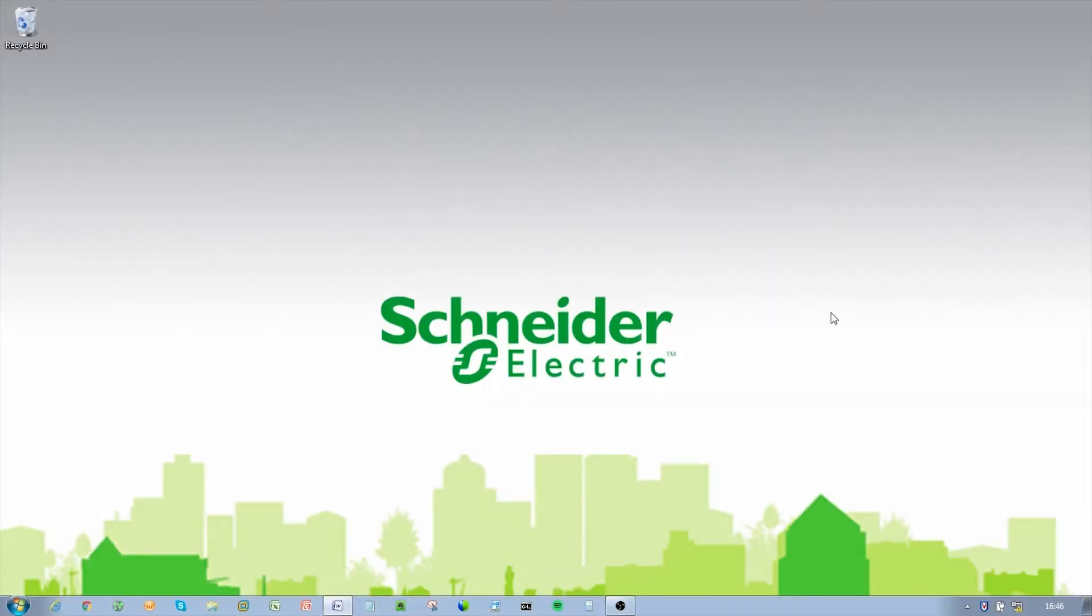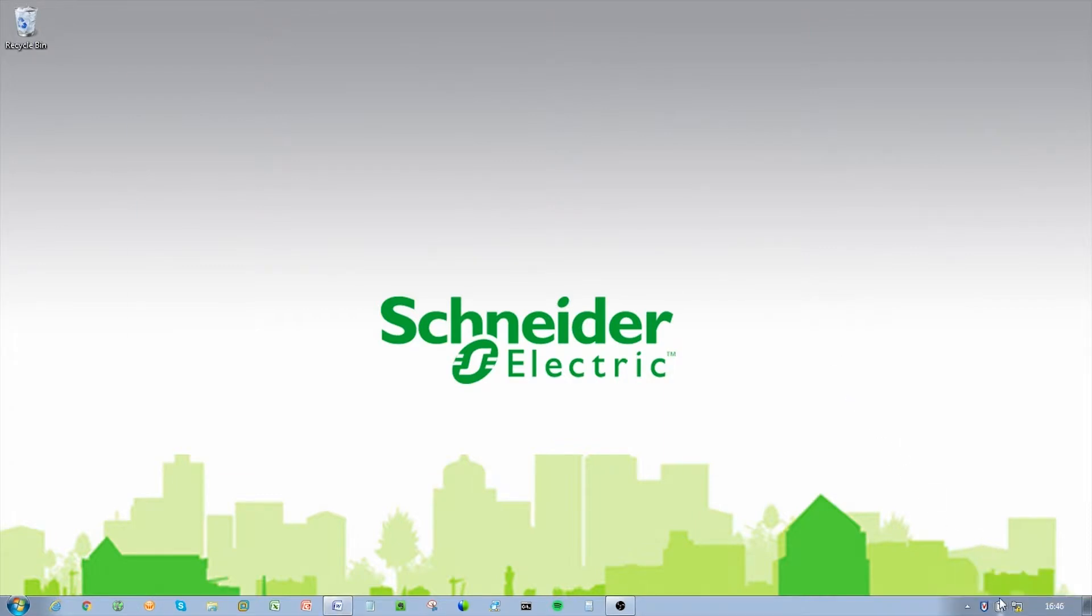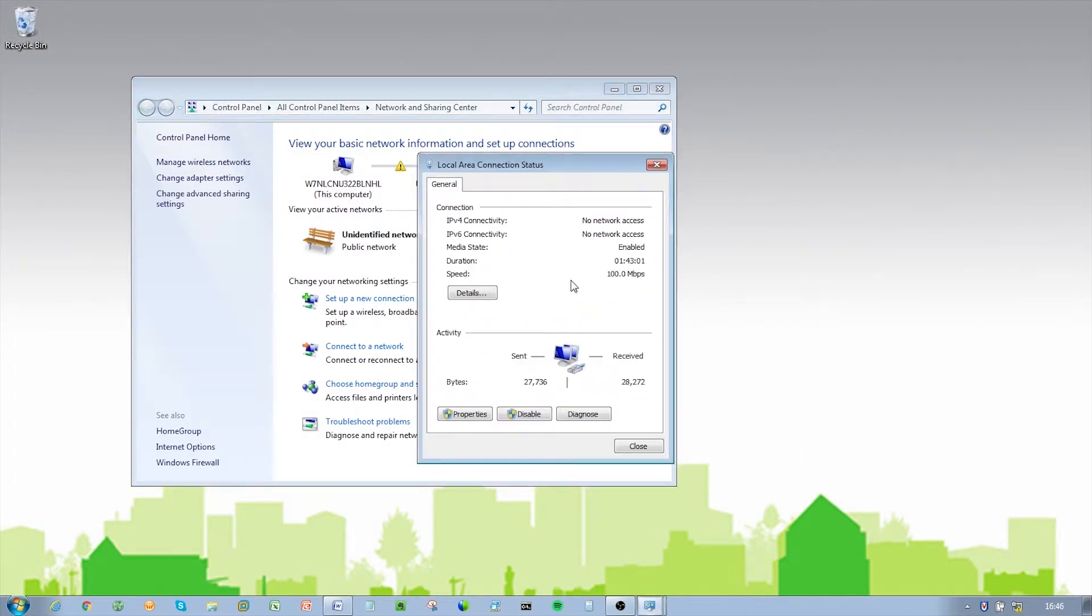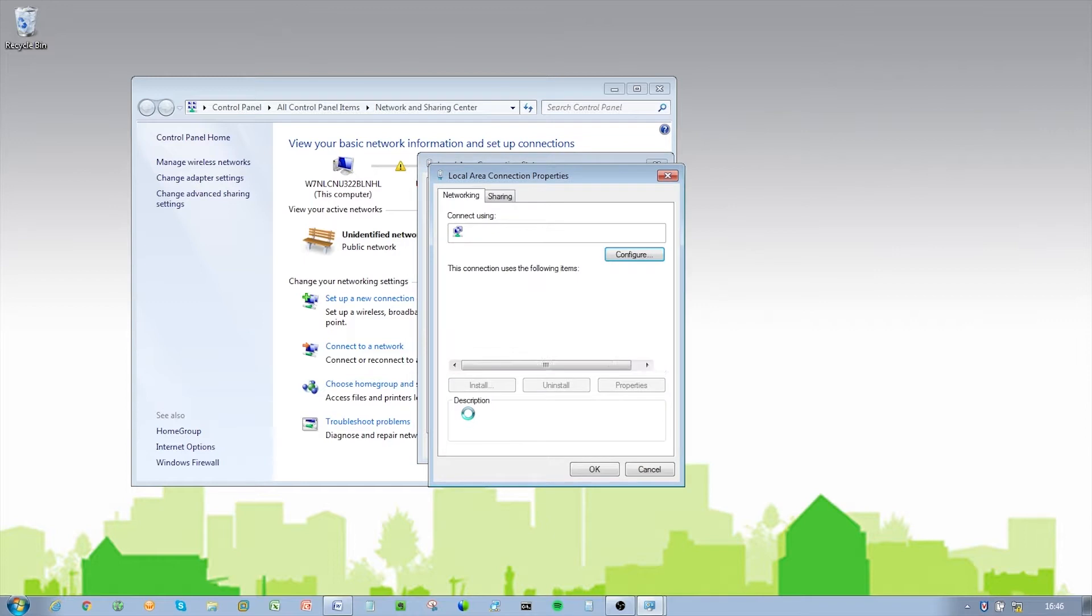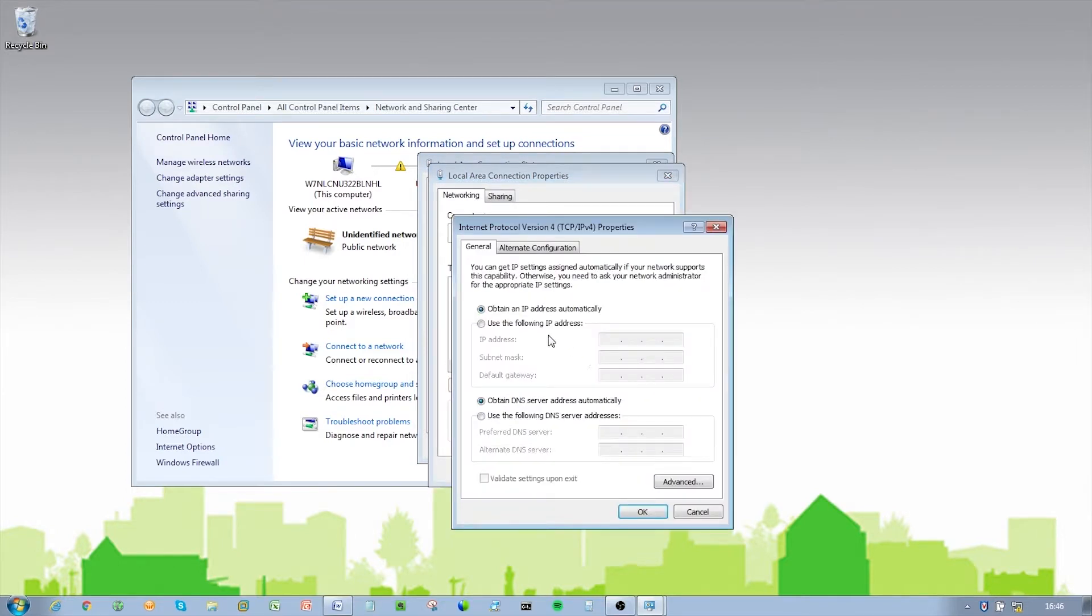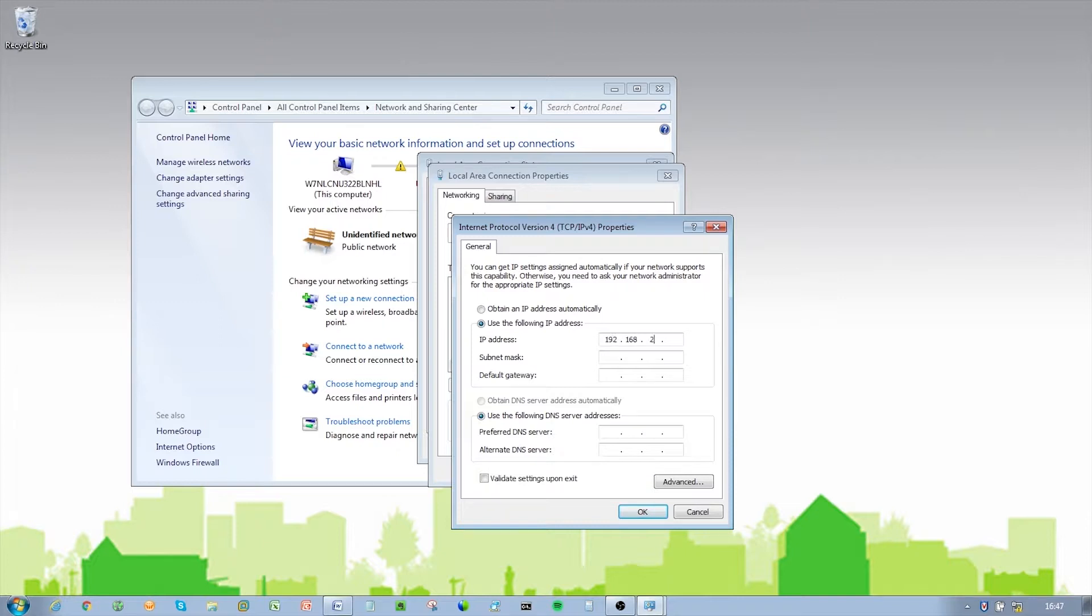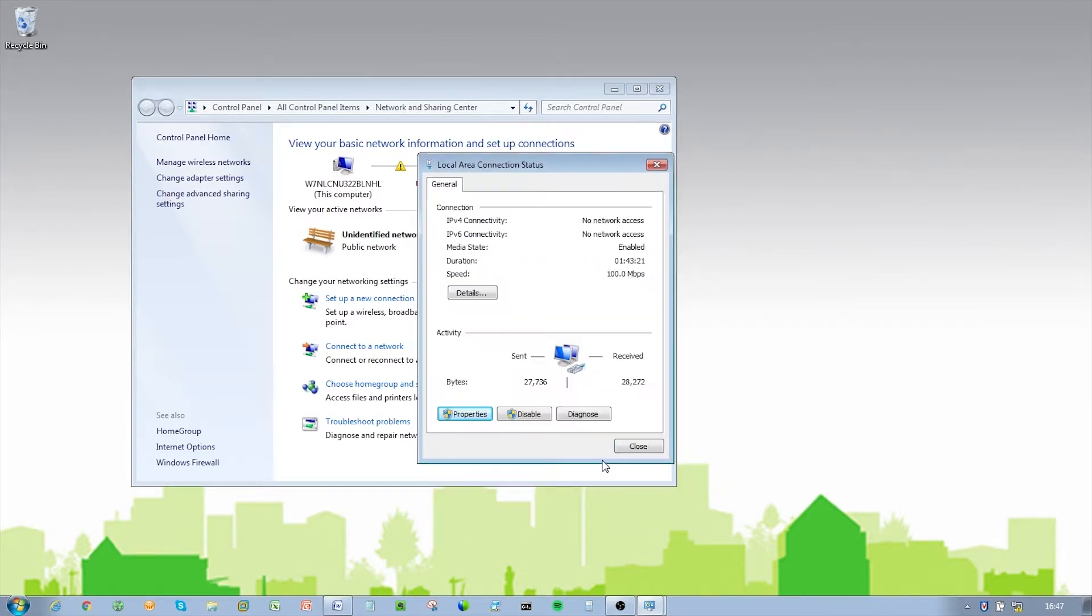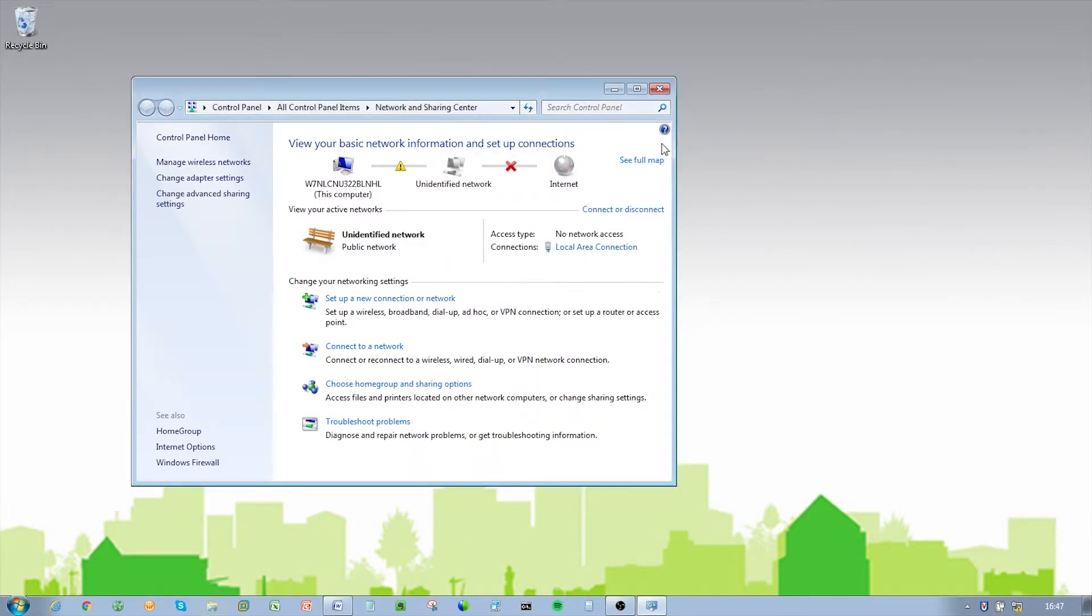To establish communication with the Trio Q data radio, ensure it has been factory cleared. The factory default IP address of the Q data radios is 192.168.2.15. You will need to set the IP of your PC in the same range, for example 192.168.2.10 with default subnet mask.